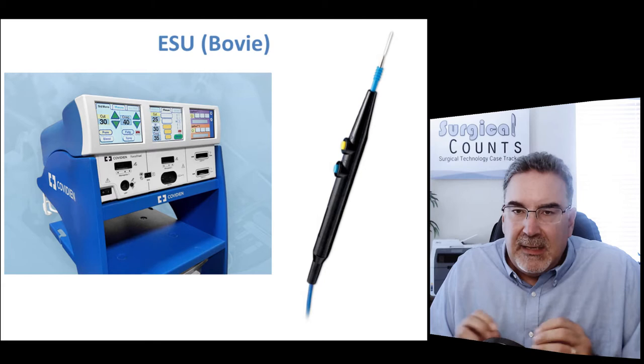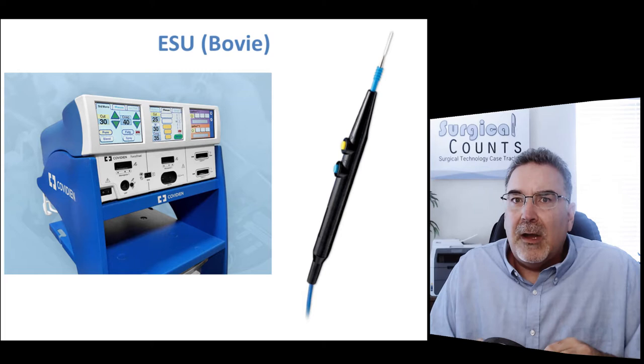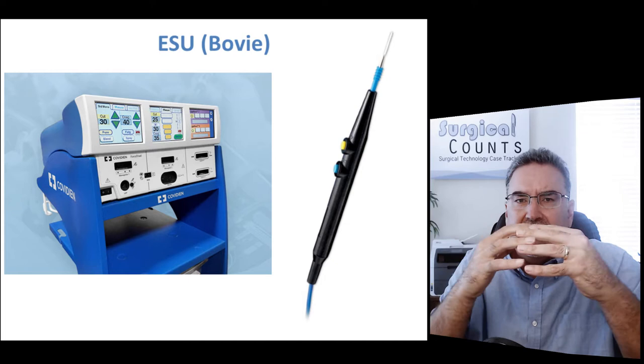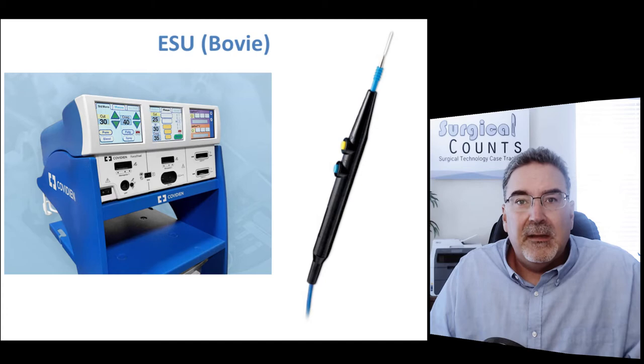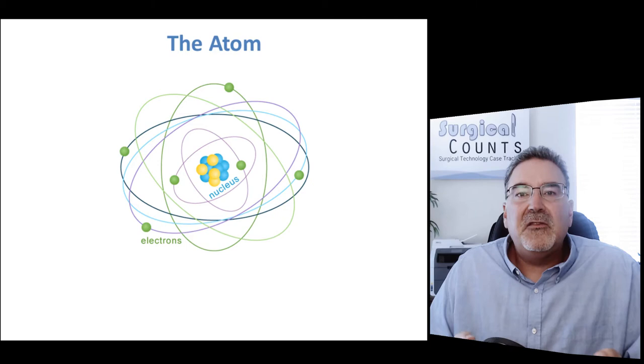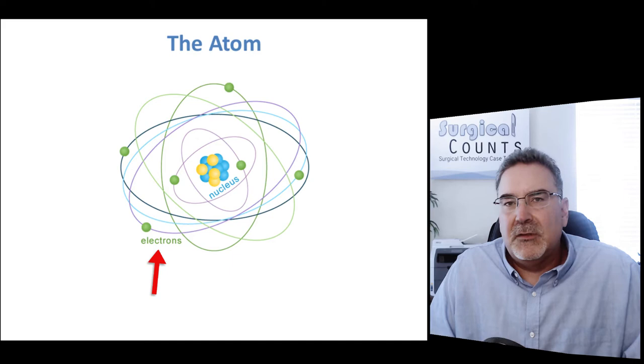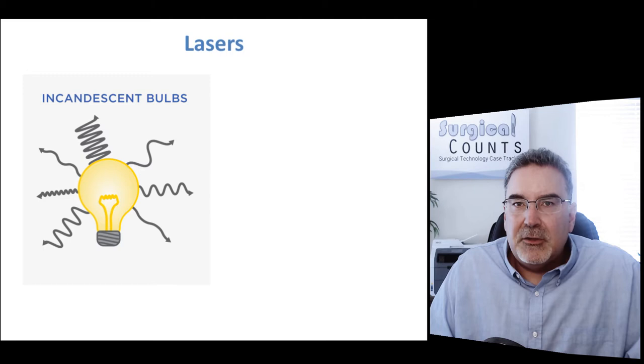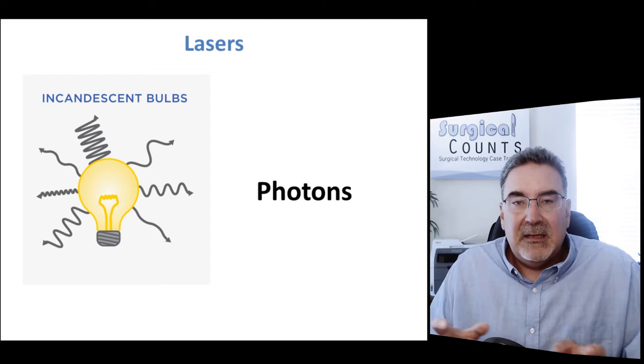The ESU uses electricity to heat up tissue to the point where it vaporizes — that's what cuts it — and then cauterizes the nearby tissue by liquefying the proteins and letting them solidify to seal off blood vessels, preventing bleeding and oozing. The ESU uses electricity, and the electron is the basic component of electricity. With lasers, we use light — light is the source of energy we apply to the tissue. And the basic element of light is a photon.